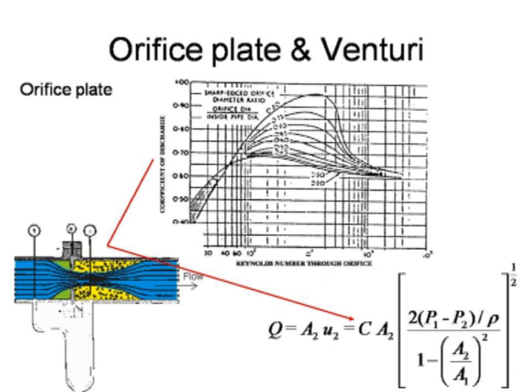So the last thing to consider is this discharge coefficient, which its name gives it away really. It's a coefficient, it's not a constant. And that coefficient depends on the Reynolds number through the orifice, and also the design. So we can have a chart, and you can see here that for Reynolds numbers really above 100, and through 1,000 to 10,000, we're typically looking at a discharge coefficient of 0.6 to 0.7-ish for this particular orifice plate. We'll change a little bit with the design of the orifice plate, maybe even getting as high as 0.9.